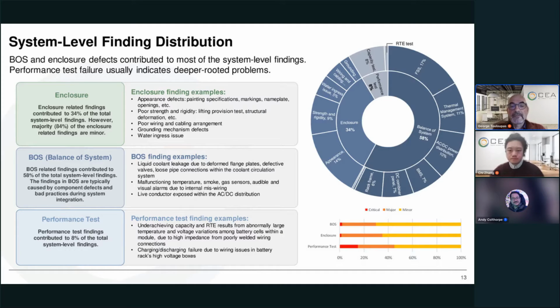rigidity issues. For example, lifting provision test, you have to lift the container because that's what's going to happen on site. And then if you put it down and the doors don't open, this is a problem, right? Also, sometimes poor wiring, cable arrangement. This can be potentially a very big risk, either for power or communication cables. Grounding can be problematic. Also, water ingress issues. So, take a water hose, throw water, and it goes in. It shouldn't happen, right? Sometimes it happens because it's a container. Maybe the doors don't seal properly, or there could be some openings where they shouldn't be.